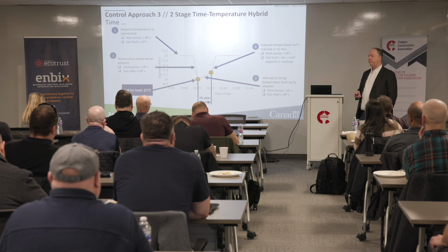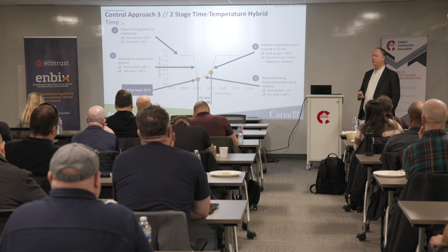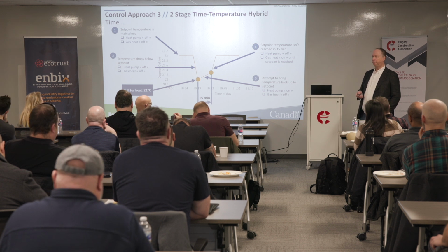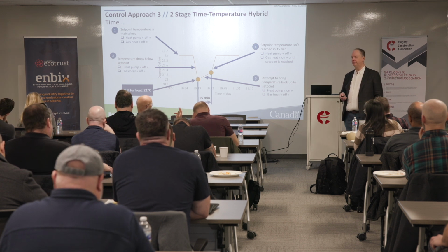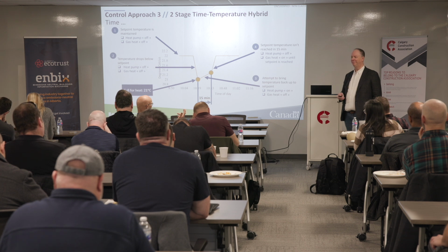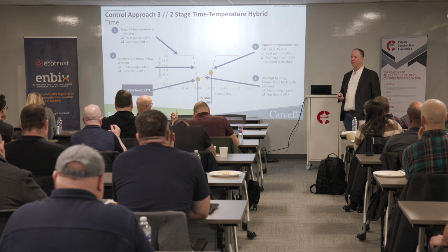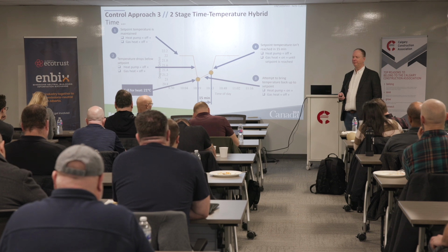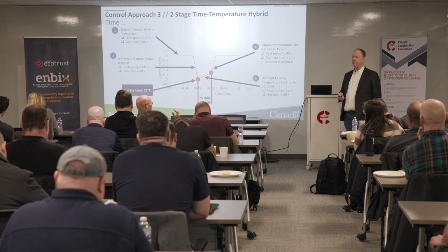That's our biggest callback: people set the temperature to 18 degrees at night and 21 in the morning, and their furnace comes on. Right off the bat, depending on the heat pump, if there's a 1.5 degree spread between setpoint and actual, it'll just go straight to the furnace. It says, I can't do that here. That's the roast versus steak thing again.